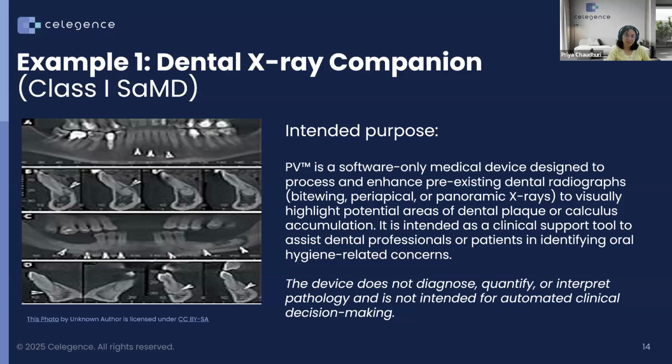It simply enhances the image to aid a professional or a physician for decision-making or patient therapeutic purpose. Because it doesn't guide treatment or automatically detect any kind of pathology, it is qualified as class 1 under Rule 11, assuming that it does not introduce any kind of risk through an active decision support.